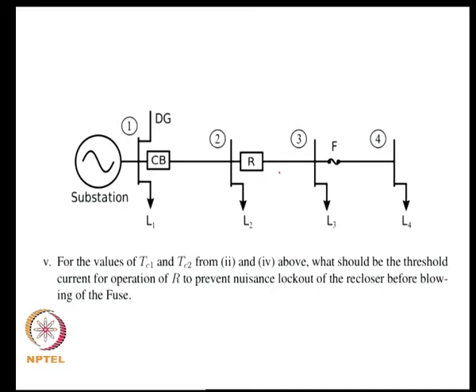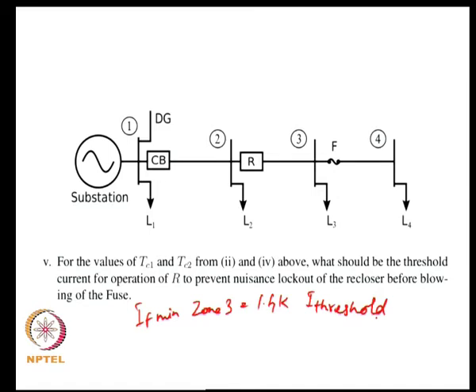A suitable threshold level can correspond to the current used for the Ifmin calculation. The Ifmin for zone 3 in the example was 1.4 kA — we could use that as a threshold, so that for current levels below that you do not have nuisance lockout of the upstream device for a fault in the downstream zone.